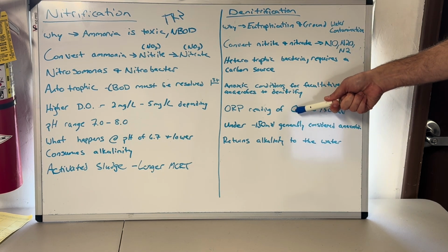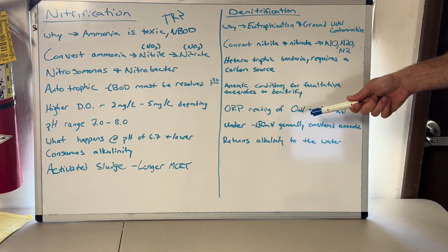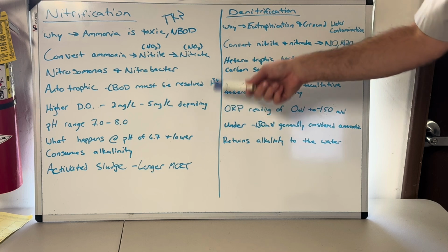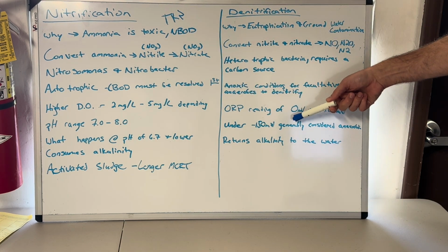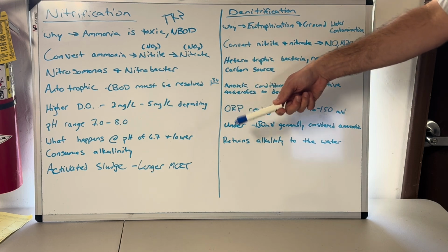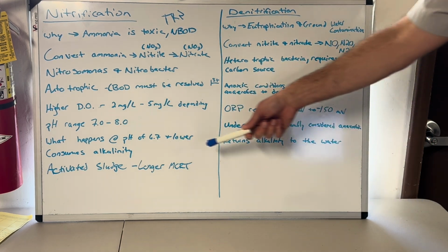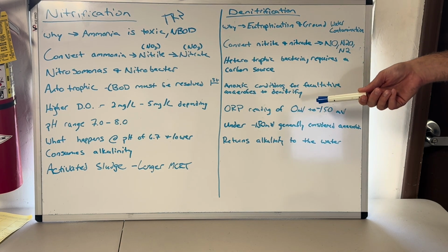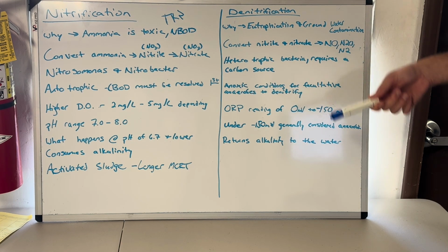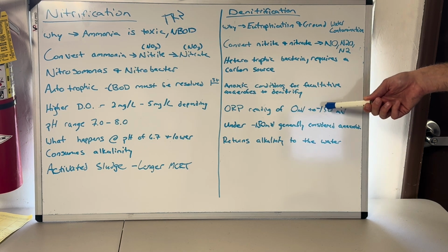I won't wait for the advanced. Too much, I might be running too much dissolved oxygen before the RAS returns. So I might need to back off my DO, or I'm not getting good oxygen uptake because something else is happening that we've already talked about, and I need to start looking there. Or my loadings just aren't as heavy as I think they are, and I need to check my food to microorganism ratio. And then if I start getting to negative 100 millivolts, I start paying attention.